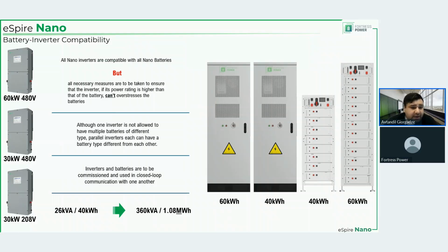Inverters and batteries are to be commissioned and used in closed loop communication with one another. Now, obviously, there's communication protocol. We include the communication cables. We expect you to use them and have the system running in closed loop communication mode, never in open loop communication mode. And we were also talking about modularity and scalability, and this is what it stands for.